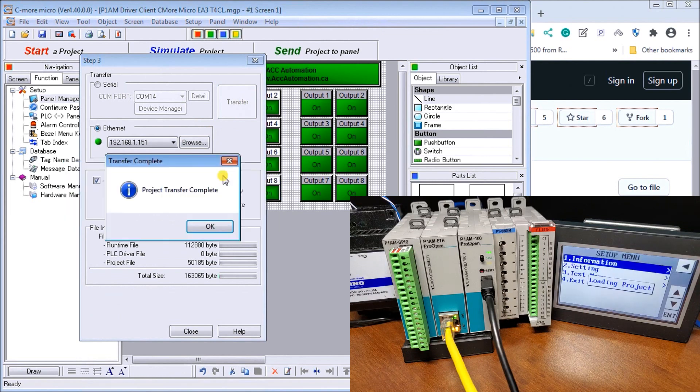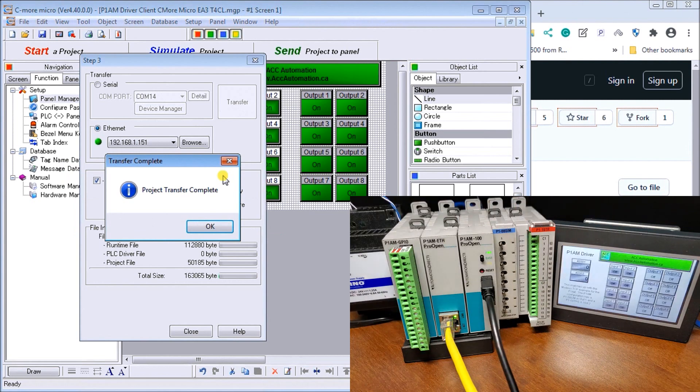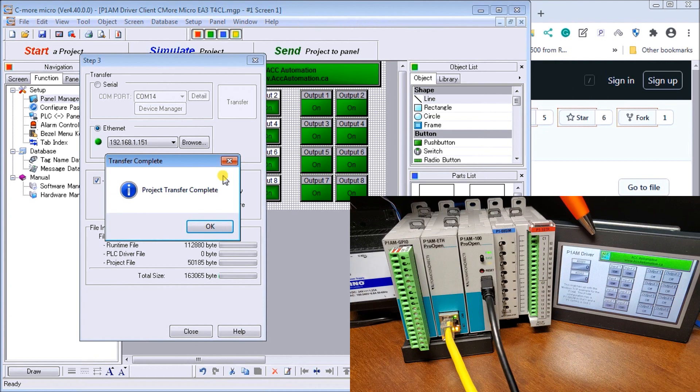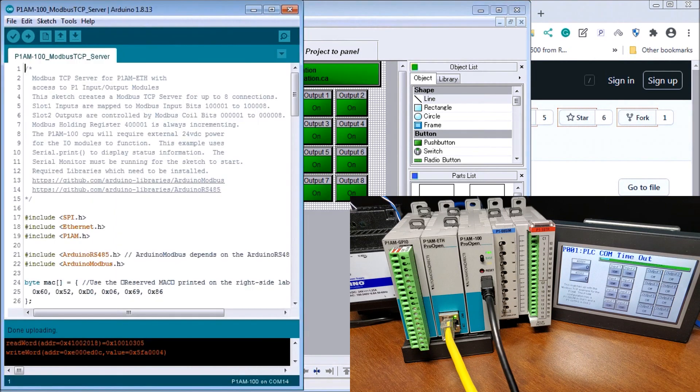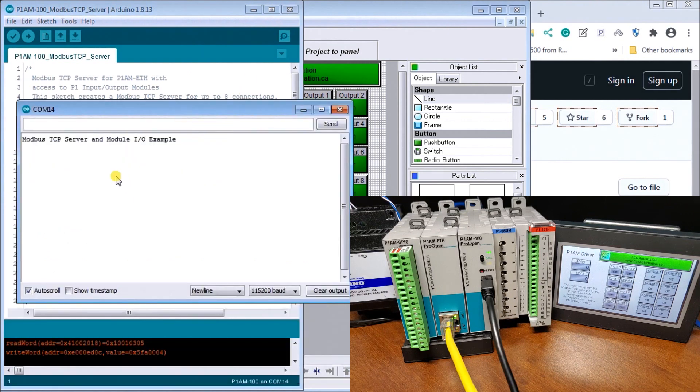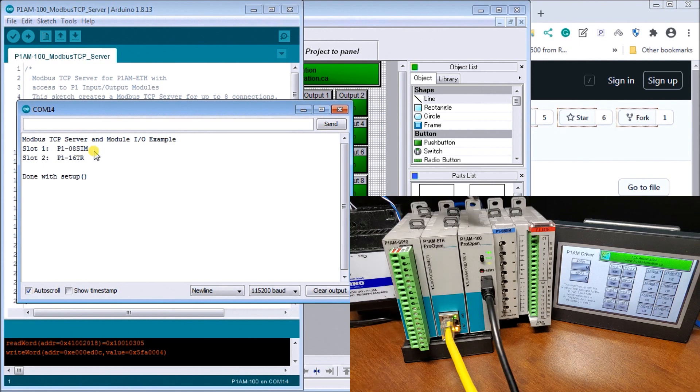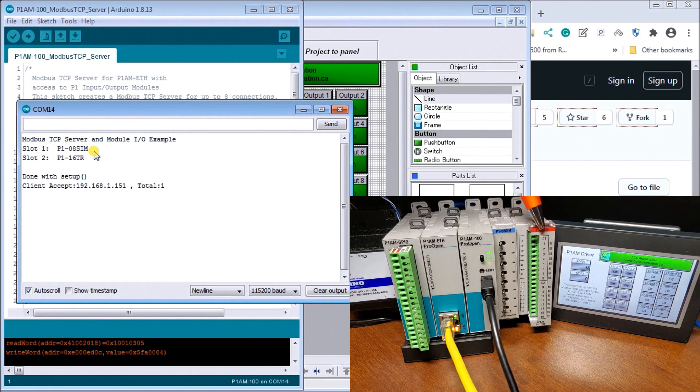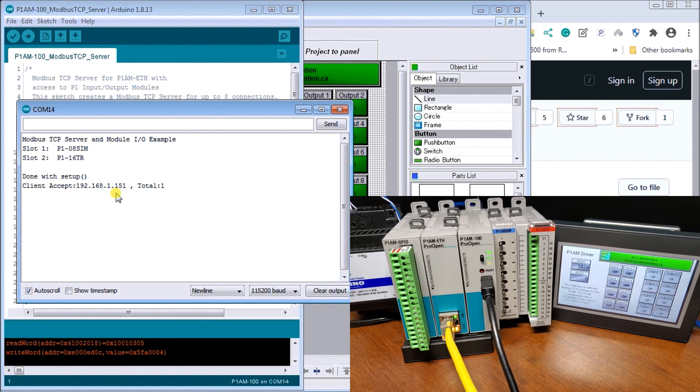And once it's done, it comes back out and you'll notice that we now have a timeout function here. And that is because we said that we have to wait for our serial communication port. So here's, I'll call it my serial port. There we go. We're waiting for our unit to take a look. It says, yes, I have slot number one. I have our simulator here, input. And on slot number two, we have our 16-bit output channel right there. And now it's waiting. It's done with the setup. And it's waiting for the client and accepted the client. And our client is 192.168.1.151, which is the exact same one where we just downloaded. So we know this is the unit that's being communicated to.